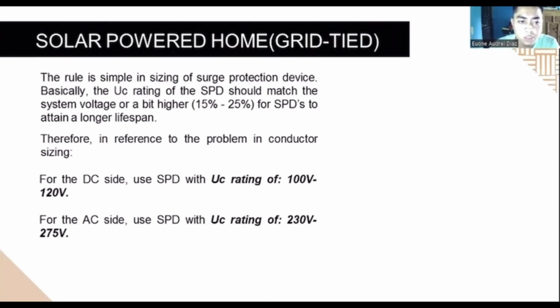The rule is simple in sizing of surge protection device. Basically, the UC rating of the SPD or the surge protection device should match the system voltage or a bit higher, 15% to 25% for SPDs to attain a longer lifespan. Therefore, in reference to the problem in conductor sizing, for the DC side, use SPD with UC rating of 100 volts to 120 volts. For the AC side, use SPD with the UC rating of 230 volts to 275 volts.